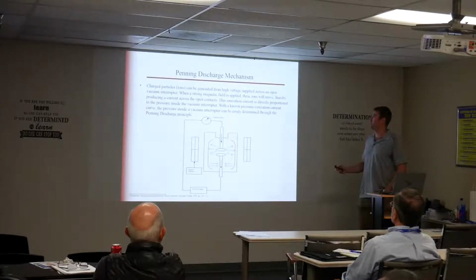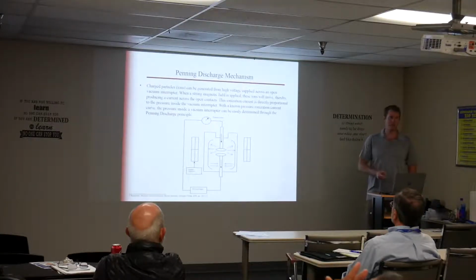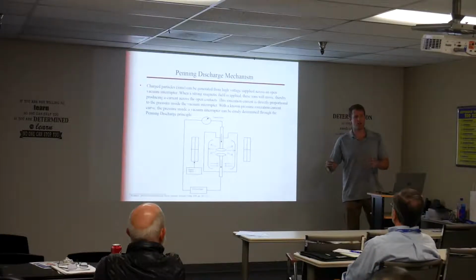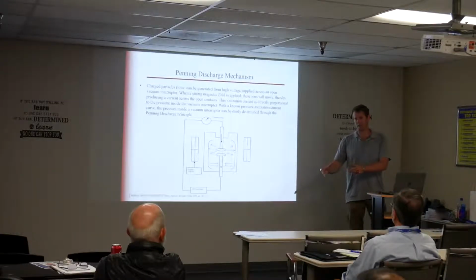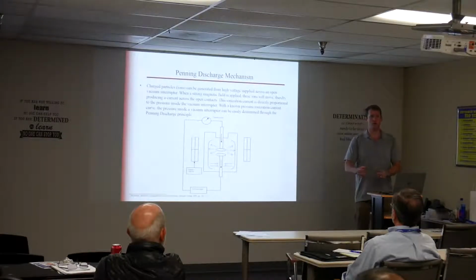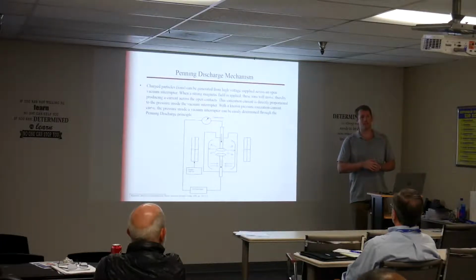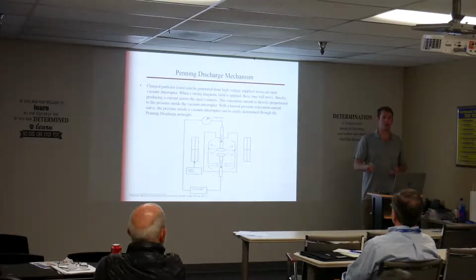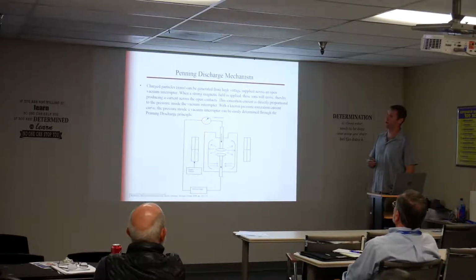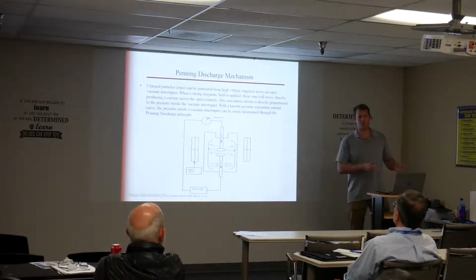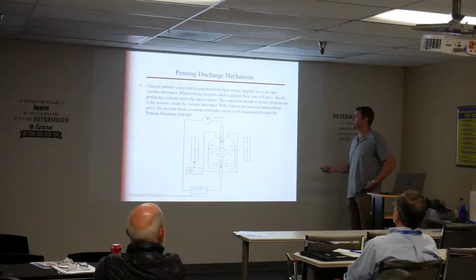So a little background on this Penning discharge, the magnetron, we didn't invent that. It was a lab-based test done in the vacuum bottle factories on loose interrupters. So somewhere overseas they make all these interrupters, they take out a sample size, they take out a couple, put it in a fixed coil, get a pressure measurement. Then they put that interrupter on a shelf for 2 weeks, take it down and test it again. With those 2 points, the pressure should get a little bit better. If it got worse, then I know there's a leak or something wrong with that. So we took that technology, and all we really came up with is a way to make a field portable test set so you can test these installed in breakers.